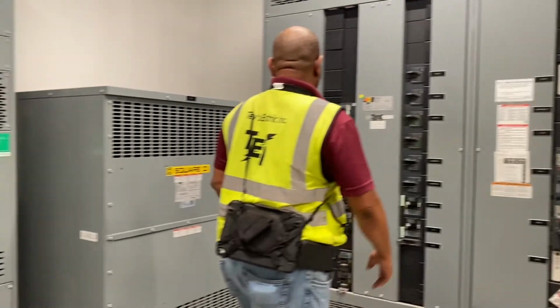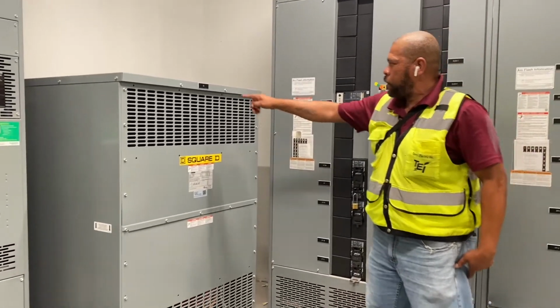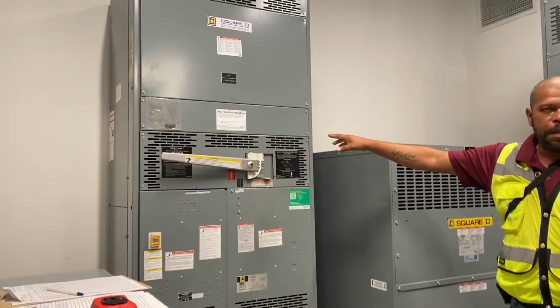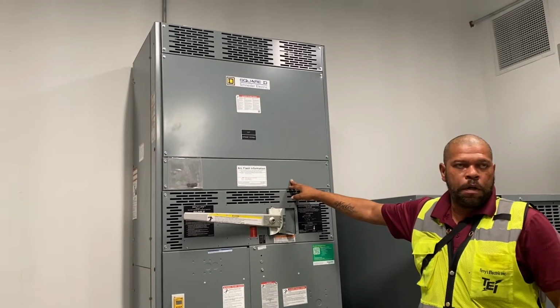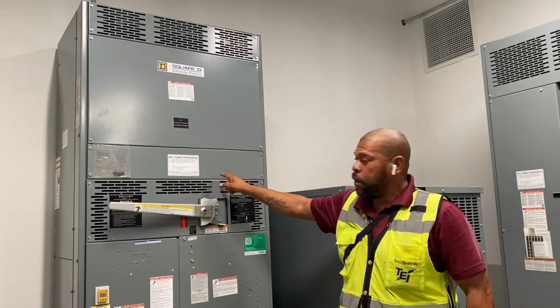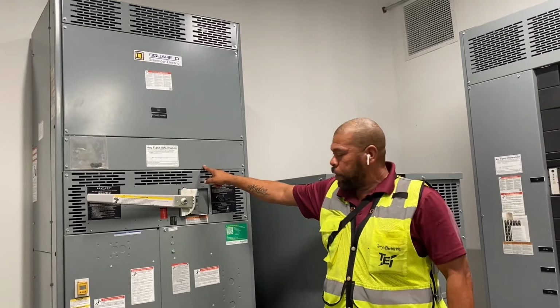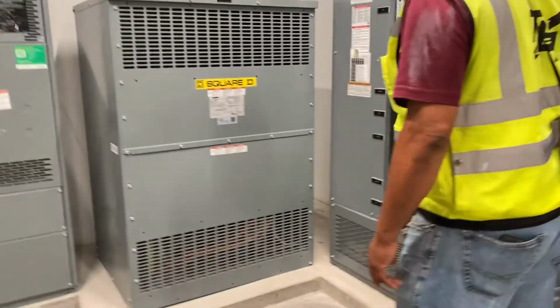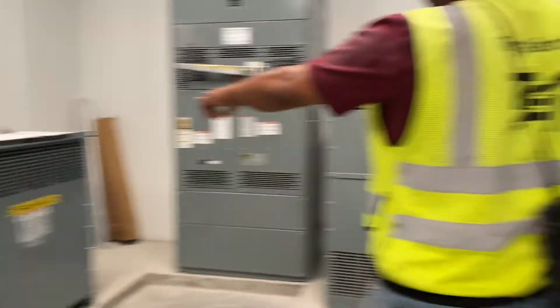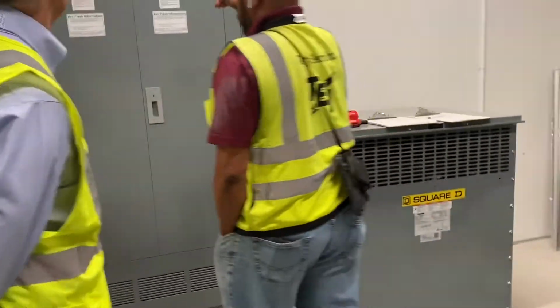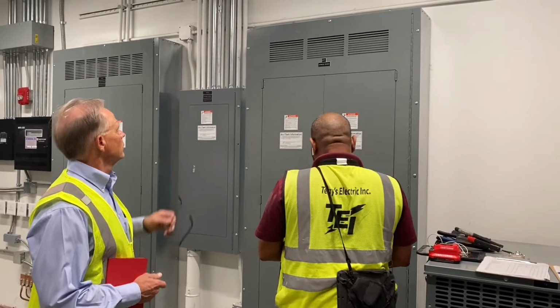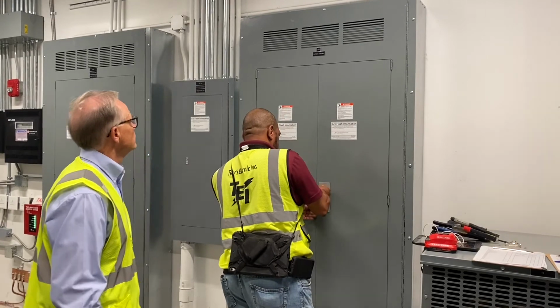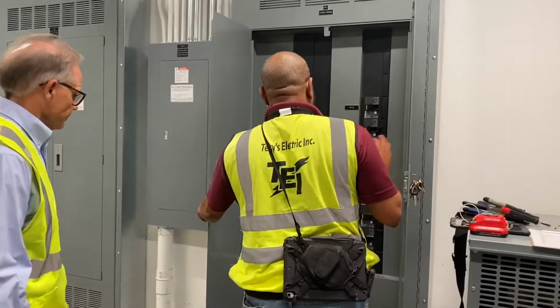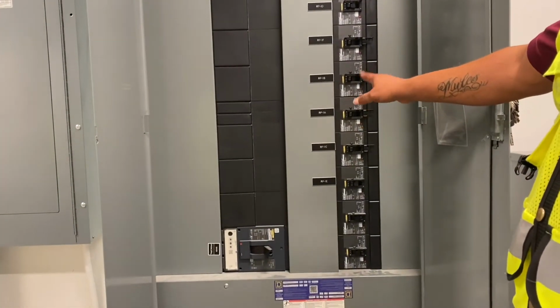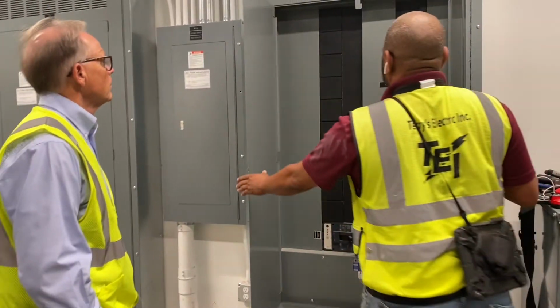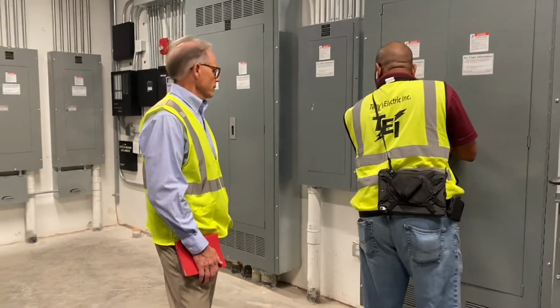These transformers over here, for instance, you've got T2 here. P2 feeds the T2 transformer, which feeds LDP right here. Now, this panel here feeds all your second floor low voltage panels. So everything on the second floor that's low voltage feeds up to LDP2. All right. Now, this one here, T1, feeds this transformer, which feeds this panel. This panel here feeds all your first floor low voltage panels. Everything's labeled. These are all the panels that it feeds on the first floor. And I'll walk you through and show you the panels that it feeds. T1, where's it labeled? Right. Oh, it's labeled.